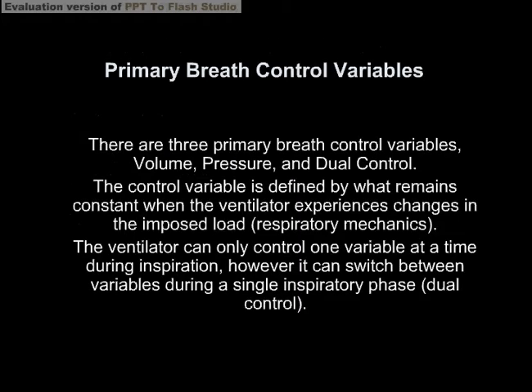Primary control variables: there are three primary breath control variables — volume, pressure, and dual control. The control variable is defined by what remains constant when the ventilator experiences changes in the imposed workload. The ventilator can only control one variable at a time during inspiration; however, it can switch between variables during a single inspiratory phase.